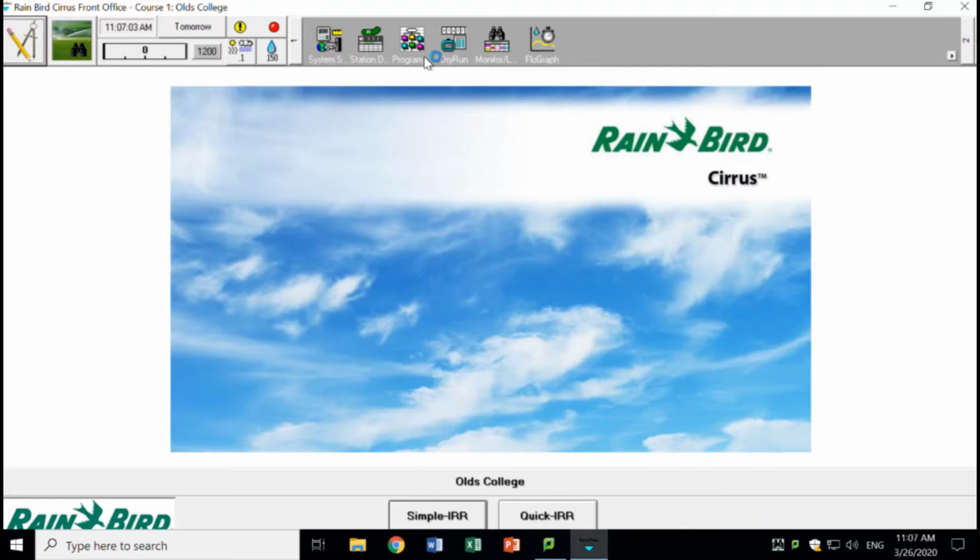Another parameter is that the program must run 3 times, one following the other. You may ask yourself, why run this program 3 times and not just one time for a long duration of time? This is because some of the low spots in the pipe will be filled with water, and the initial push of air will push a large amount of that water out, but the remaining water will just come out as mist. So what we're doing is having that large initial push through the first program. Second program also has a large push. Third program should get the remaining water out.